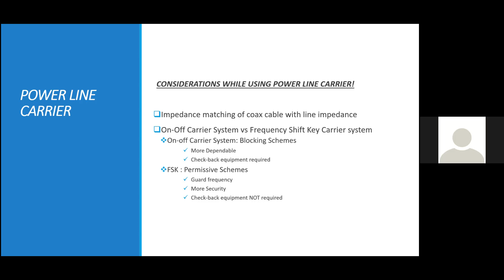If the guard frequency drops, there is an alarm which turns high if we lose a transmission line or the line tuner by any fault. And on the on-off carrier system, we need a check back to check the carrier. But on the frequency shift carrier system, we do not need a check back because we have the guard frequency to prove the health of the carrier communication channel.